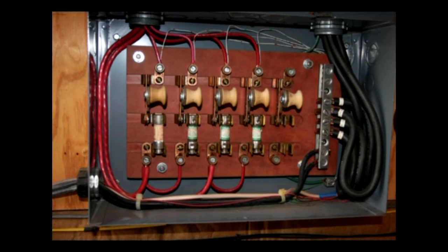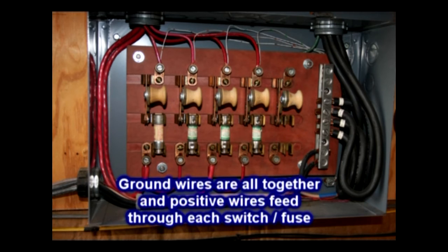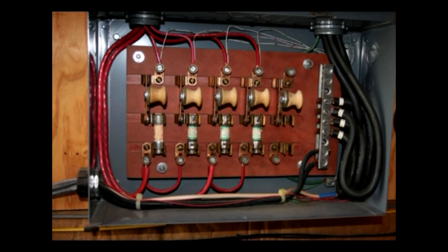Here's where the panels come in, to 4 fused switches. This system is about 15 years old, so switches and fuses were used, though circuit breakers could also be used in this position - just 4 DC breakers in a box, each fed by a different panel array. You can duplicate this for as many panel arrays as you have, or not separate them, but it gives more flexibility in case you want to take one offline to work on it.